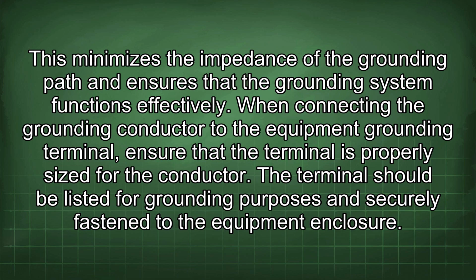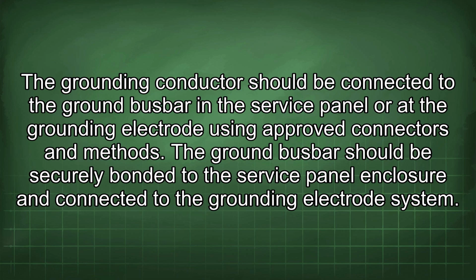When connecting the grounding conductor to the equipment grounding terminal, ensure that the terminal is properly sized for the conductor. The terminal should be listed for grounding purposes and securely fastened to the equipment enclosure. The grounding conductor should be connected to the ground busbar in the service panel or the grounding electrode using approved connectors and methods. The ground busbar should be securely bonded to the service panel enclosure and connected to the grounding electrode system.